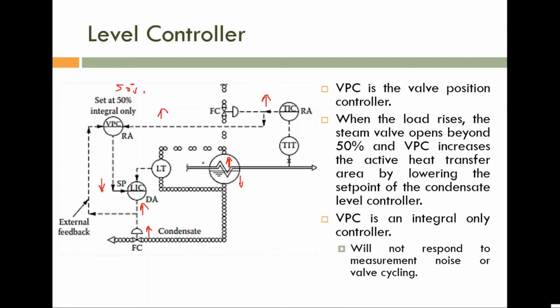So now we can correlate one by one. Okay. So if this temperature measurement is small, TIC is giving a large control signal. So definitely this control valve will act accordingly. Forget about that, we are not discussing this control valve. So if temperature measurement is small, TIC control output is increased. So the measurement of VPC is also increased. The set point of VPC is fixed.